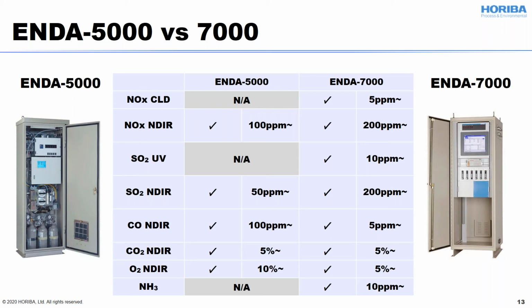Even today we are going to talk about the ENDA-5000 series. However, HORIBA also has the ENDA-7000 series. I just bring these slides to avoid confusion here, because both ENDA are developed for continuous emission monitoring system, which is called the CEMS. This slide is showing a comparison table. As you can see, ENDA-5000 only has NDIR analysis and MPaO2, while ENDA-7000 has chemiluminescence NOx analyzer and the UV SO2.